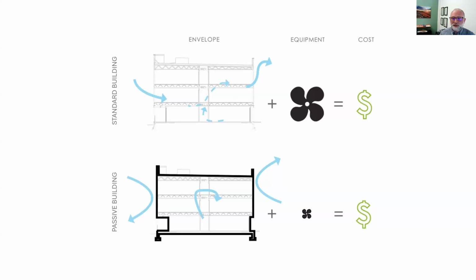Because of the need for cooling and dehumidification in many of the US climate zones, it's often impractical to eliminate a system as we can in Germany. But the same logic applies. We can apply rigorous design principles to take advantage of the well-insulated, tight Passive House envelope and to downsize and simplify the mechanical system. The objective being to shift costs from the systems to the building envelope and thereby invest in the parts of the building that have a longer useful life, increase comfort, and reduce the life cycle cost of the building.